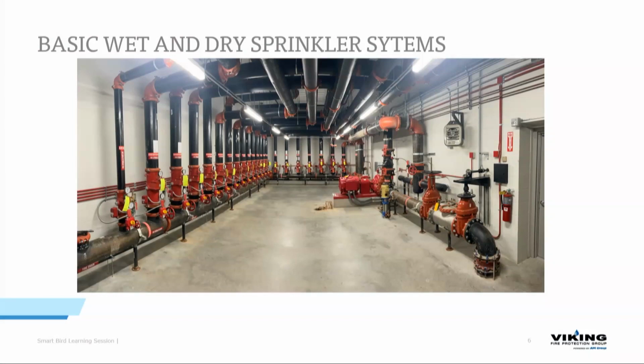and a drain. On some of these you also do see a white placard here, and basically all that indicates is those are the systems that we used in our hydraulic calculations to determine that the system works. So a lot of times those are missing, and that's a really, really big issue with FM. So in your facility, if you do not have the hydraulic placards, it can be quite an issue. A little bit of reverse engineering needs to take place.